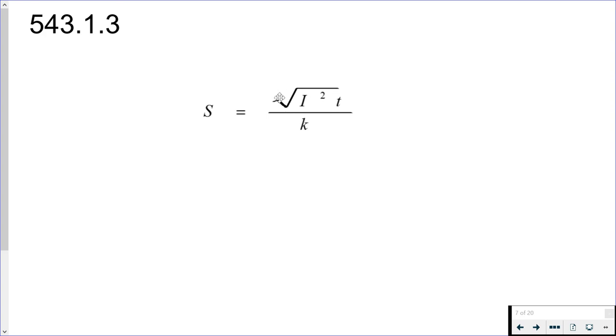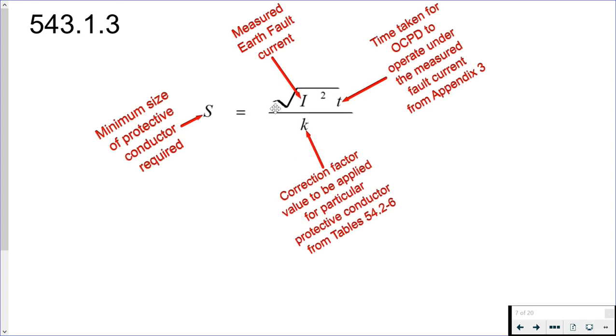The calculation method identifies this adiabatic equation. The key tells you that S is the minimum size of protective conductor that's required. I is the measured fault current. T is the time that it takes the overcurrent protective device, in this instance the fuses that are in the service head, to operate with this fault current flowing. And then K, well that's a correction factor that we apply depending upon the type of protective conductor, and we find that correction factor from tables 54.2 all the way through to table 54.6.